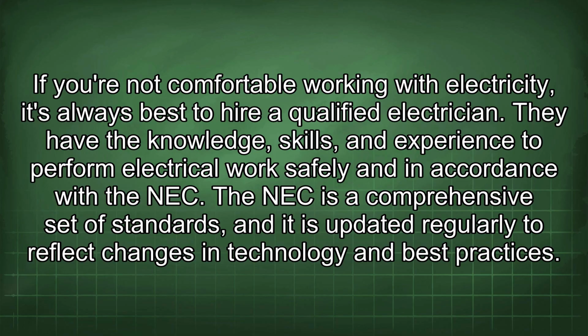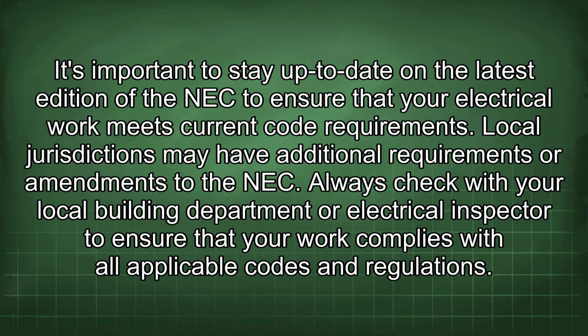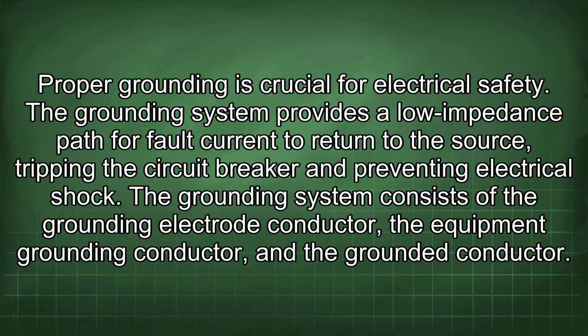The NEC is a comprehensive set of standards, and it is updated regularly to reflect changes in technology and best practices. It's important to stay up to date on the latest edition of the NEC to ensure that your electrical work meets current code requirements. Local jurisdictions may have additional requirements or amendments to the NEC. Always check with your local building department or electrical inspector to ensure that your work complies with all applicable codes and regulations. Proper grounding is crucial for electrical safety. The grounding system provides a low impedance path for fault current to return to the source, tripping the circuit breaker and preventing electrical shock.